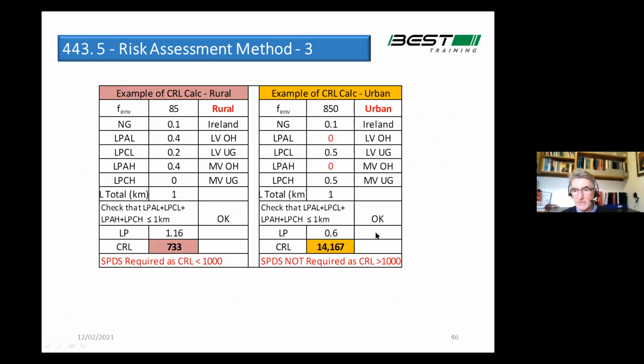When you come to an urban network, the environmental factor is 850 to start off, and most modern urban networks don't have a lot of overhead cables on them. The old ones sure do. The old residential areas all have overhead lines, but modern ones don't. It's all underground network, and you're always going to get a figure higher than 1,000. So if you want to do that and take the risk, but I would say put them in everywhere, because this is purely lightning, risk of lightning strike is all you're looking at here.